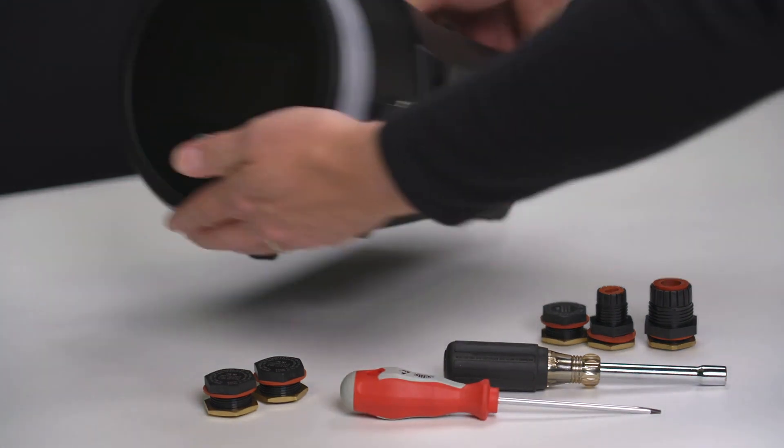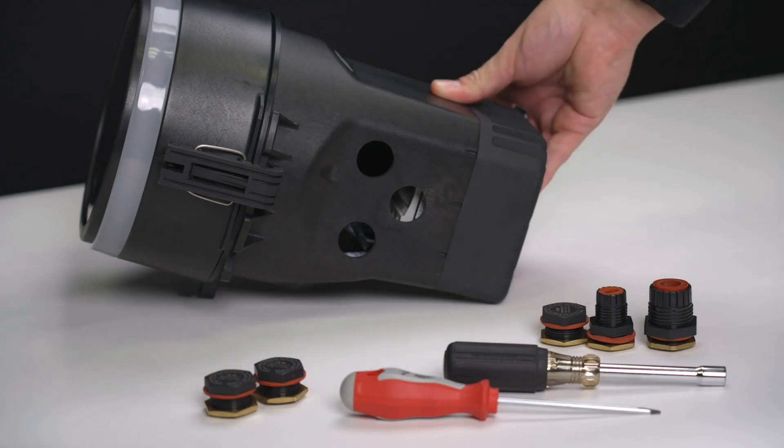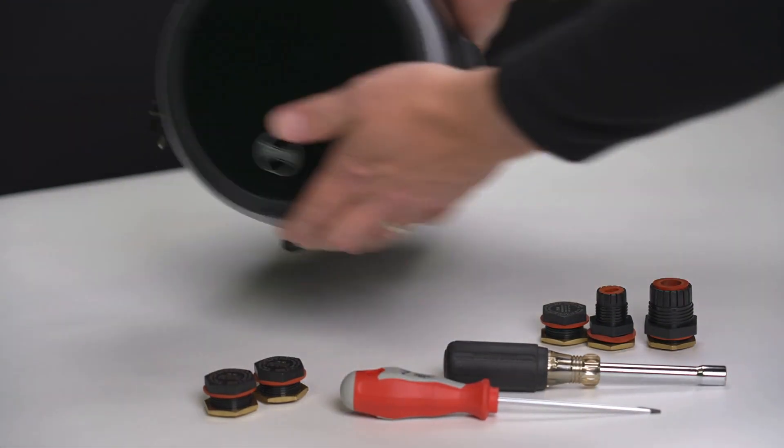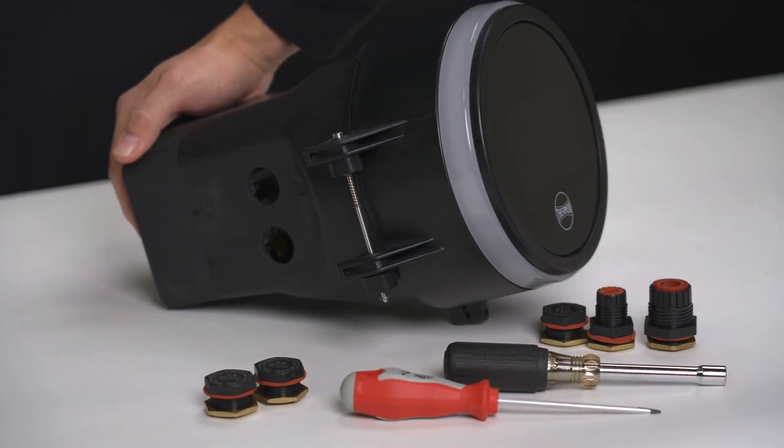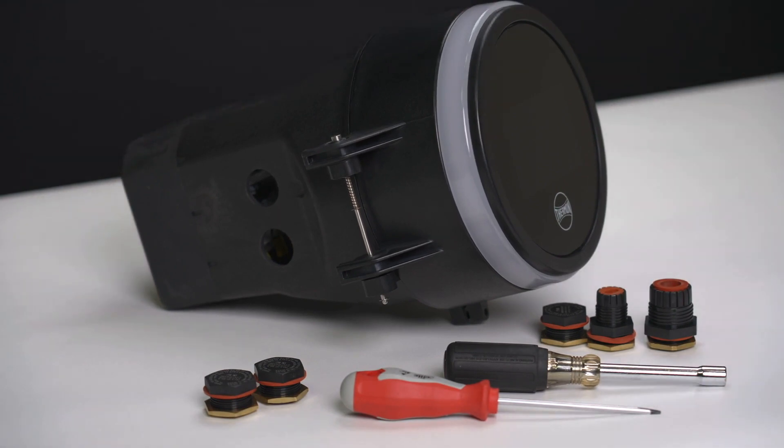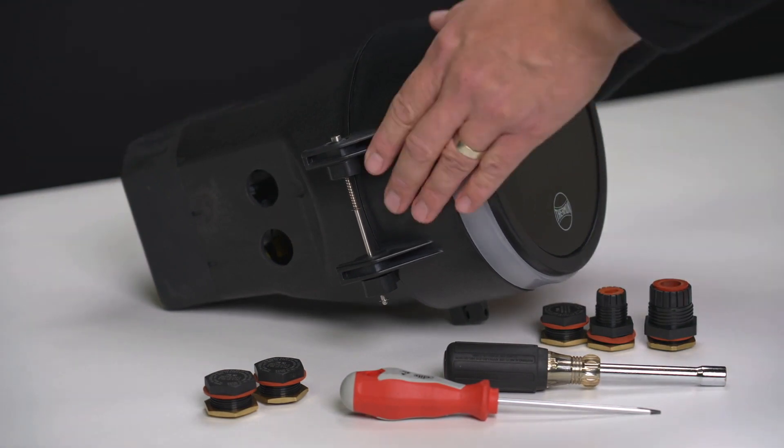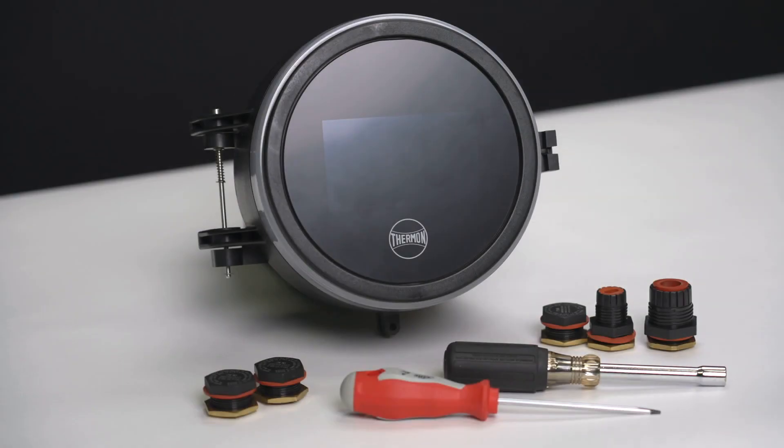The unit can have up to five entries, three on one side and two on the other. These are M25 clearance holes. Glands shall be selected for the cable types used and must also meet local codes. Tools required to complete the prep are a flathead screwdriver to access the terminals and 5/16th nut driver.